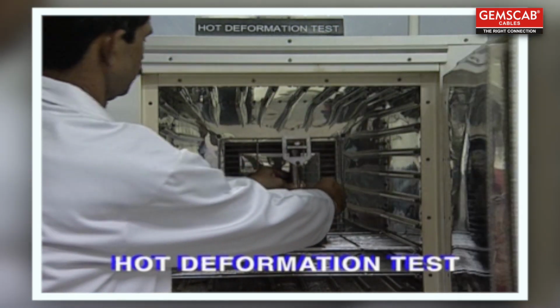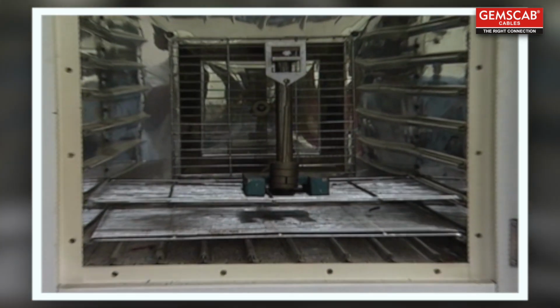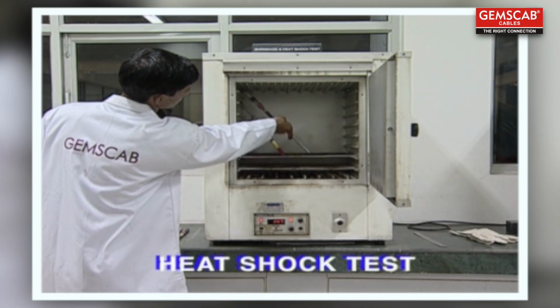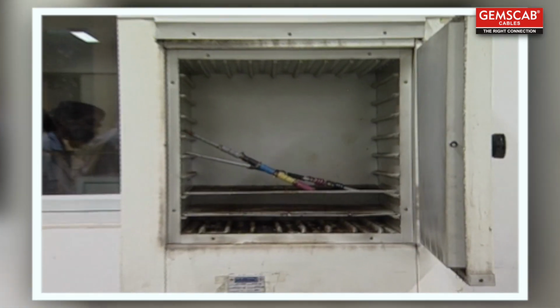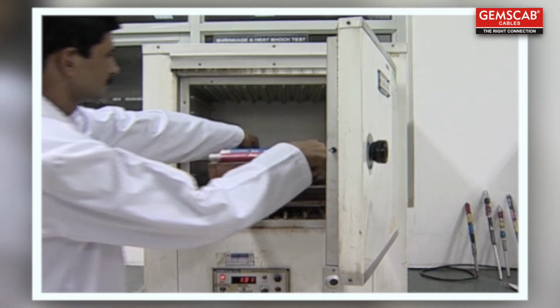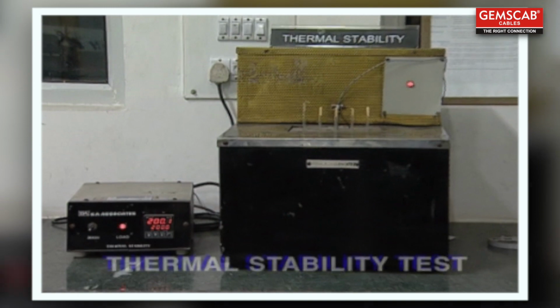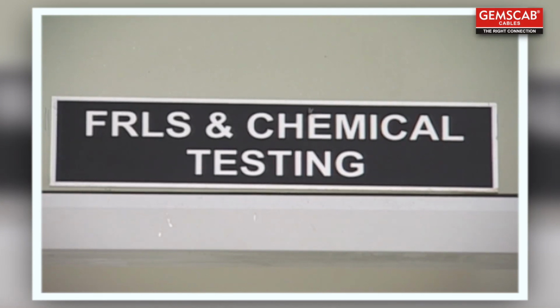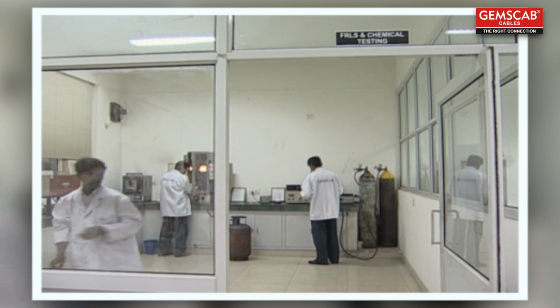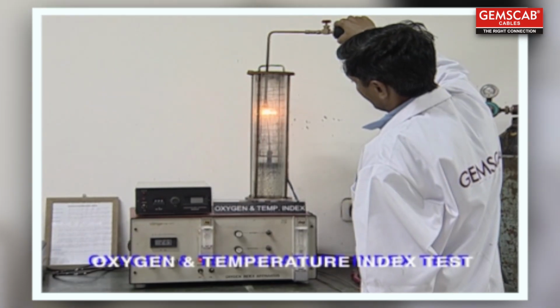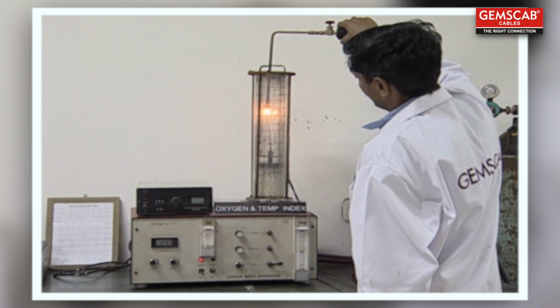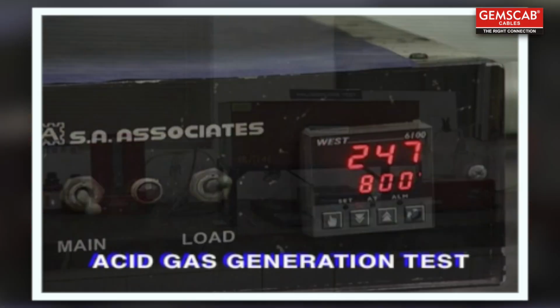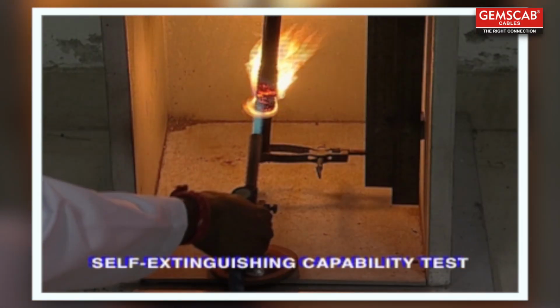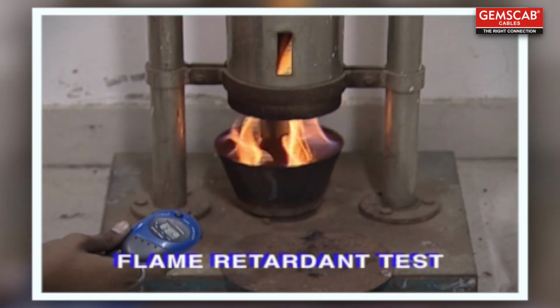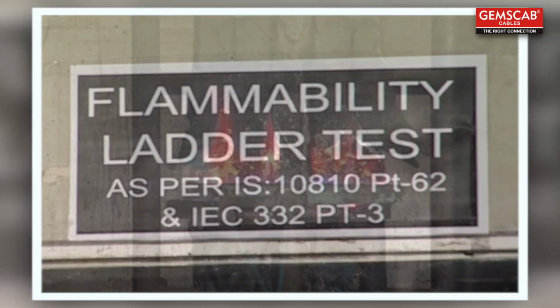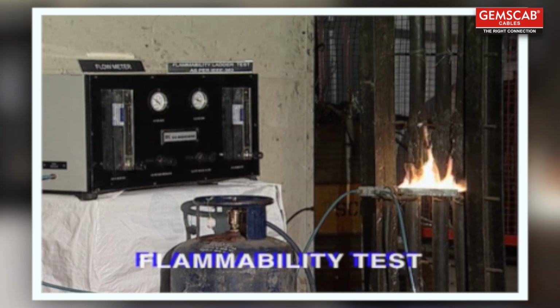Whereas the hot deformation test checks the thermoplastic material for sufficient resistance to heat, the heat shock test checks the resistance of insulating material to thermal changes. Other critical tests include the shrinkage test and the thermal stability test. Numerous special tests are also carried out on FR and FRLS cables. These include the oxygen and temperature index test, the smoke density test, the acid gas generation test, self-extinguishing capability test, the flame retardant or Swedish chimney test, and the flammability test to check the cable's flame propagation properties.